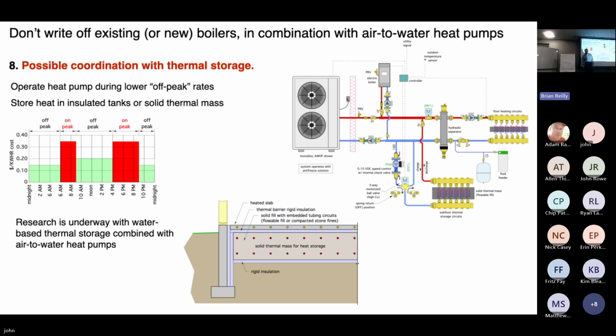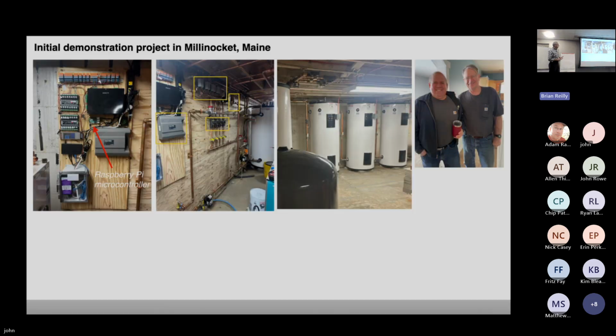And again, I don't want to get into the details, but that's a hydronic system that would be capable of sending heat from the heat pump into this during off-peak rates, and then extracting heat from this and putting it into some kind of a heat emitter system in the building. I think this is really one of the major frontiers going forward for hydronics, is the combination of time of use rate structures of some form, as well as combination with heat pumps and thermal storage. And leads me to this.